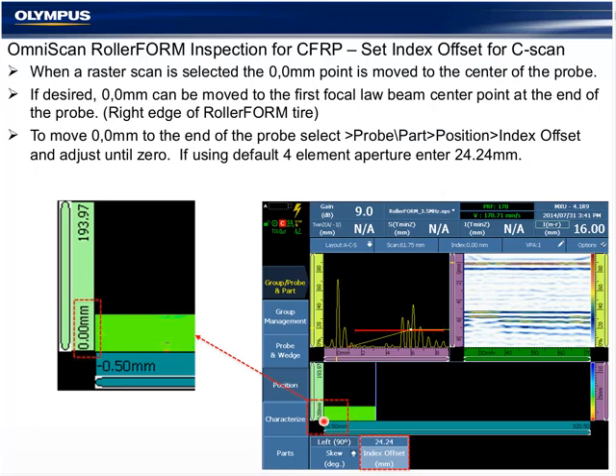Most customers prefer to move 0, 0 onto wheel probe type inspections to the far right beam center point of focal law or A-scan number 1. Whatever number you see here as a result of the aperture you programmed, entering a number opposite that, in this case 24 instead of -24, will offset this value back to 0, 0. This indicates that 0, 0 is directly under the first A-scan of beam center point number 1.